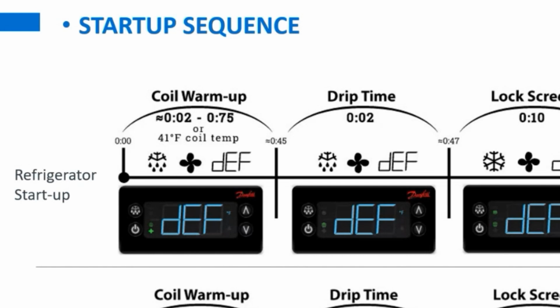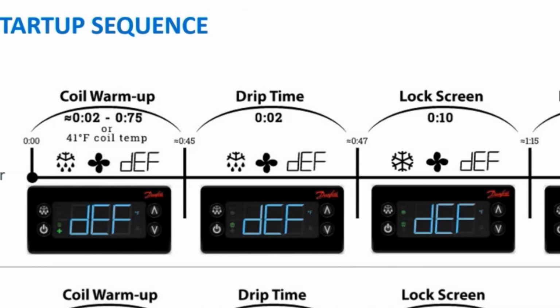As you can see in startup, we go through a defrost on a cooler. Our fans are running because it's an air over defrost. That will last anywhere from 2 to 75 minutes or a 41-degree coil. Presumably, you'll hit the 41 degrees long before you hit 75. From there, you go through a slight drip time. Of course, the fan, you'll see the icons again.